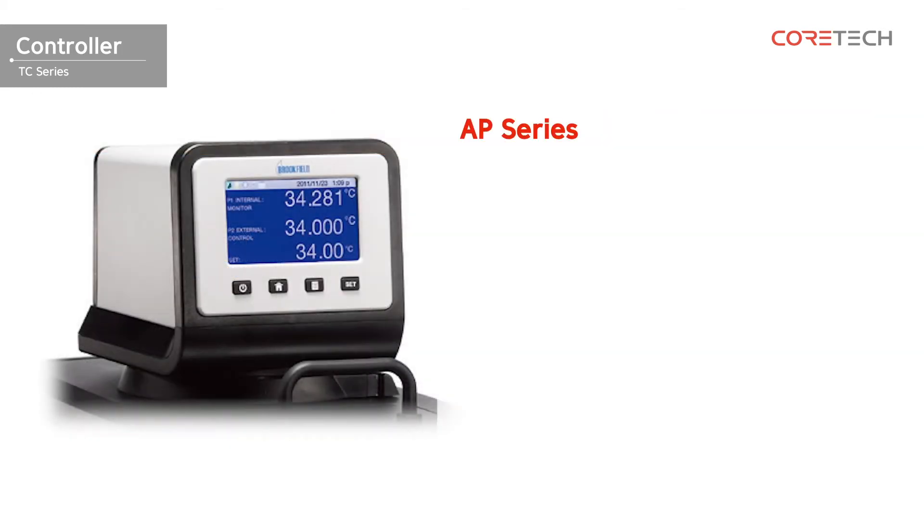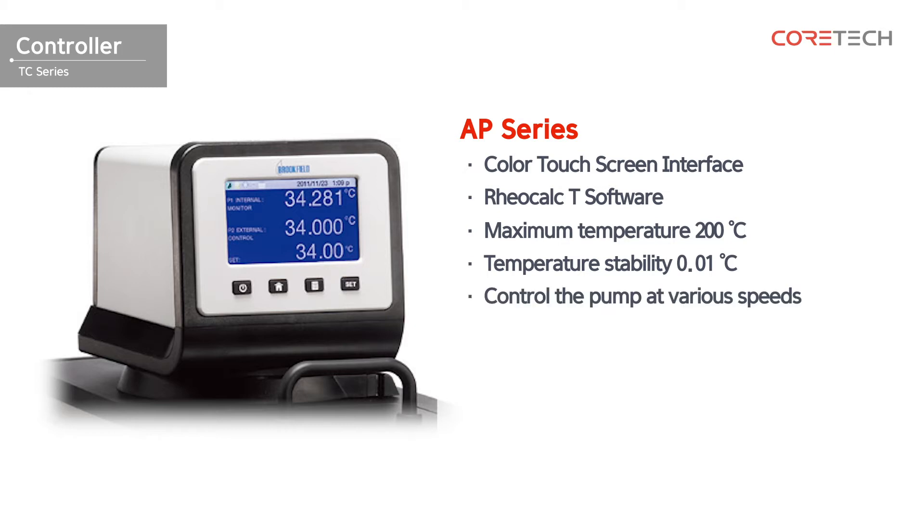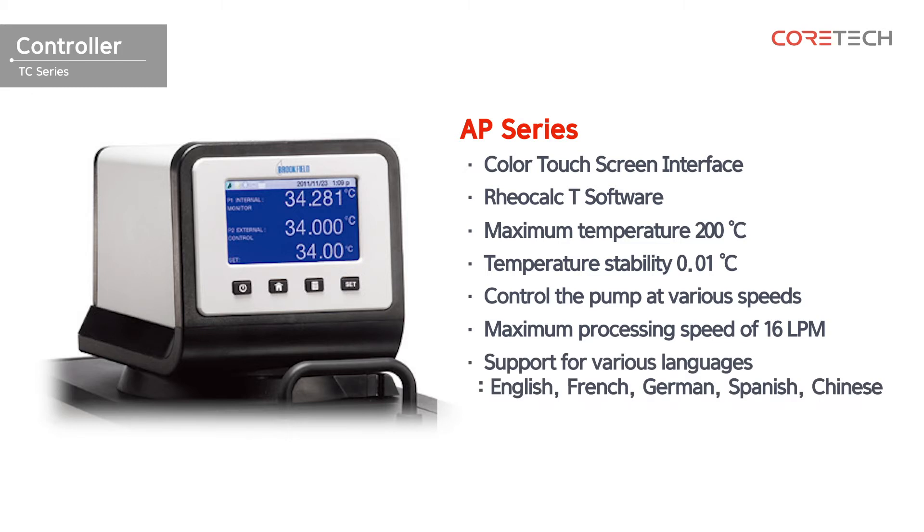This is the AP series. It is equipped with a color touch screen interface. Step setting and PC control are possible through the Rheocalc T software. It also allows temperature settings up to 200 degrees Celsius and ensures temperature stability of 0.01 degrees. The AP series can control the pump at various speeds, with a maximum flow rate of 16 LPM. It also supports a variety of languages and has a help menu.